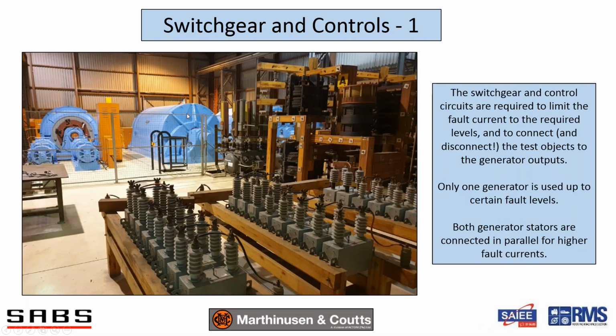Okay, then you've got the system. You generate this high voltage, and you need to produce different levels of fault currents for different times into different test objects. So this is a view from the one end. Most of the other views are taken from the far end here. Now this is from inside the switchgear compartment. Here you see the switchgear. So it's switchgear and reactors, a whole range of reactors in order to generate the required fault current into the devices.